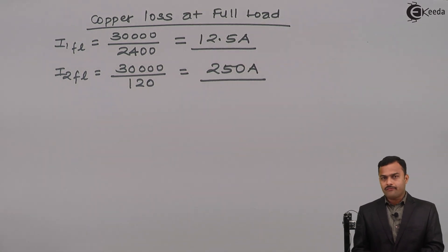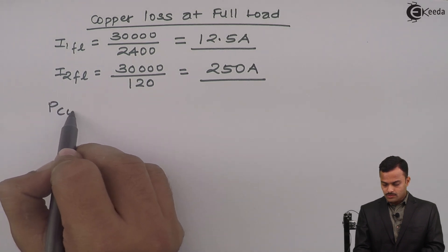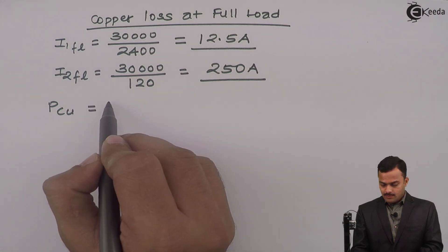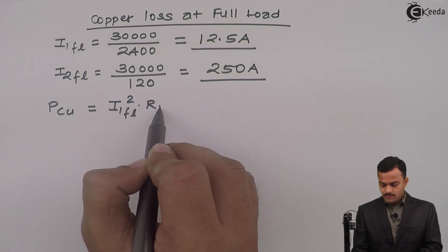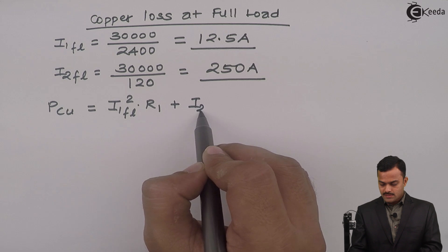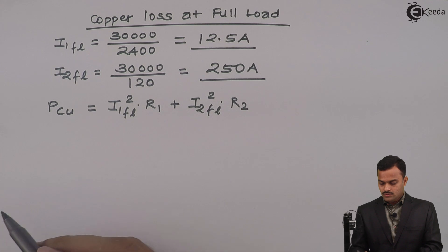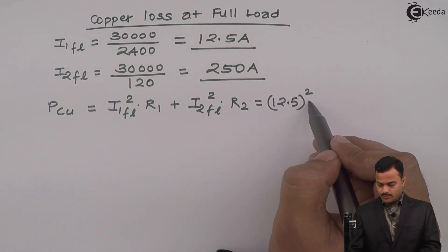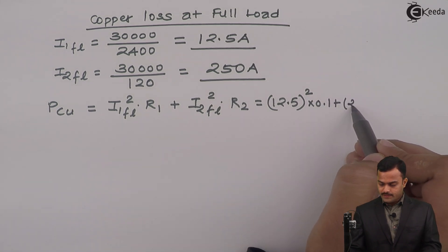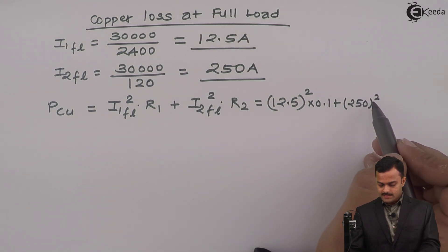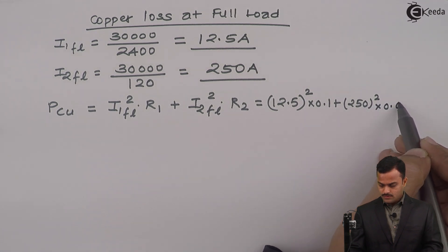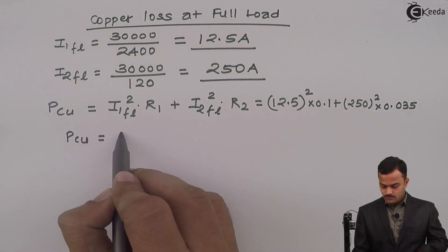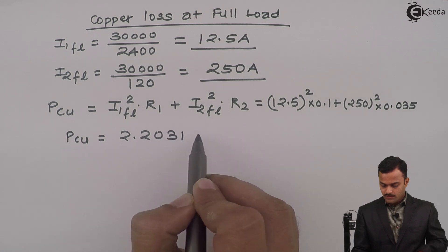Total copper loss at full load equals the sum of losses in both windings: copper loss = I1FL² × R1 + I2FL² × R2 = 12.5² × 0.1 + 250² × 0.035 = 15.625 + 2187.5 = 2.2031 kilowatt.